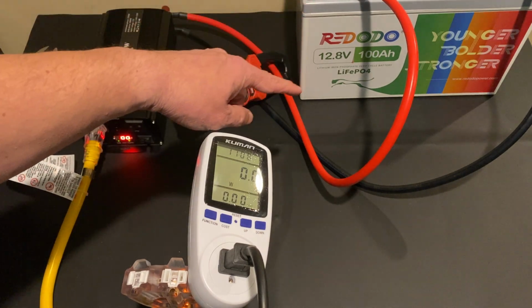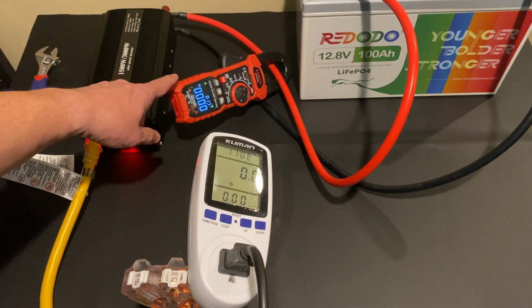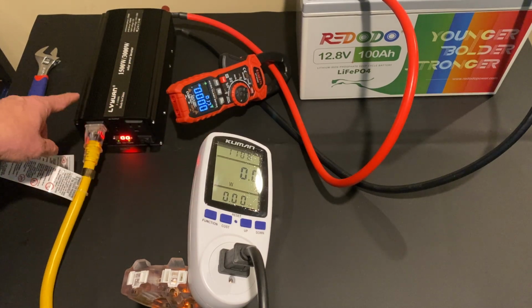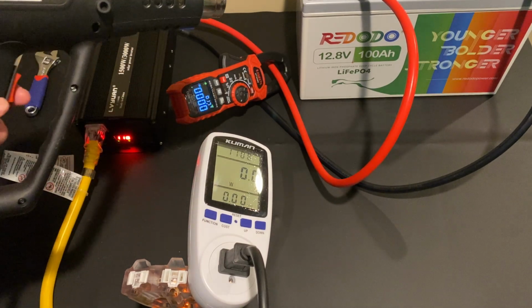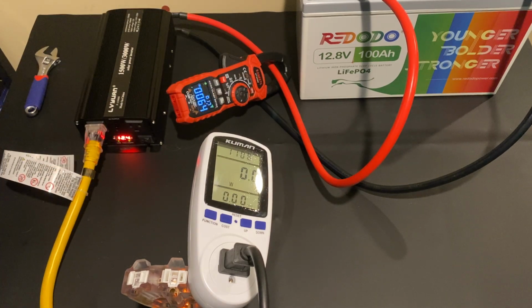You can see we have the Redodo battery connected up to the inverter. We have our Kaiweets meter, clamp-on meter measuring amps, and the Kuman watt meter. The Kuman watt meter is fed from the yellow extension cord coming out of the inverter. We're going to use everybody's favorite, the heat gun from Harbor Freight. We kick that on and we got 65 amps coming out of the battery, and the watt meter is saying we're a little over 700 watts. Now if you look at the LED panel on the front of the inverter, it's saying 530. It's also telling us the output and input voltages, which is pretty handy. But I think that 530 watts is off. I think the Kuman is a little bit more accurate, so we might have a little bit of an issue there.